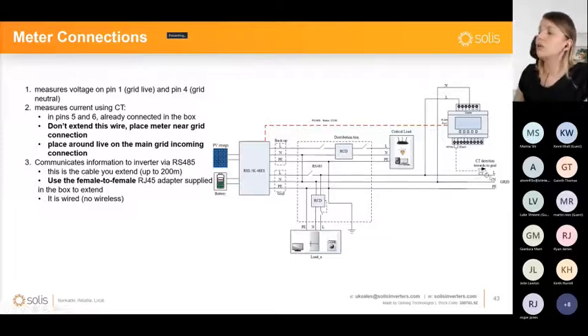The CT clamp normally has an arrow on it. That arrow usually points towards the grid. But if that CT clamp is not installed in the correct direction, the flow of energy will be displayed reversed on the meter. I will show you some tips and tricks on how to test that, just to make sure that it is installed properly. It's really easy to find out.